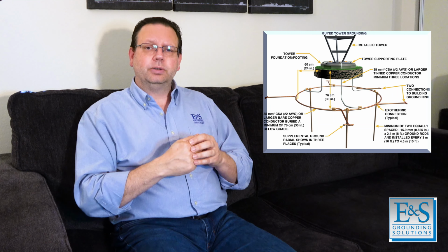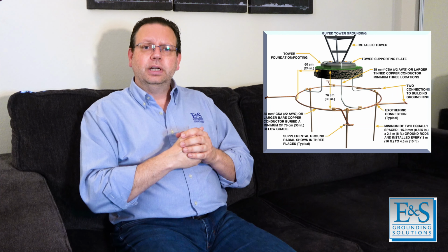These are the single best electrode system you can have for safety and for effective grounding, reduction of electromagnetic interference, and lower resistance ground. Every factor, a ground ring is ideal. But that's not what most times when you hear the old timer talk about a ground loop is talking about. They're talking about causing normal operating neutral currents to travel back on the ground system in violation of NEC 250.6.